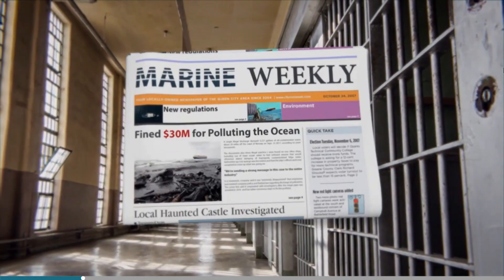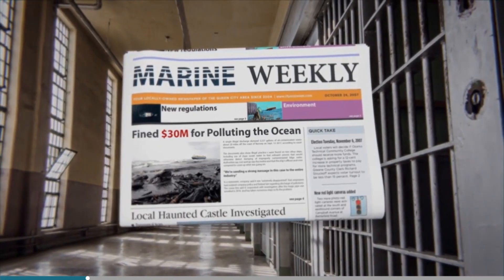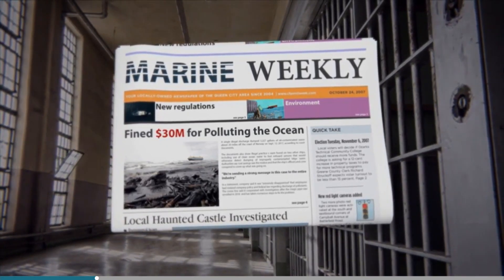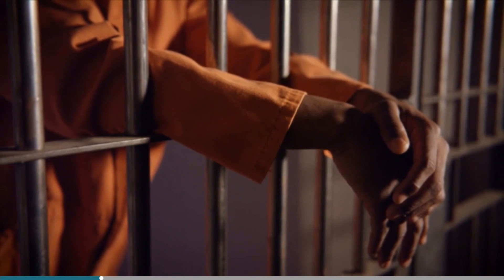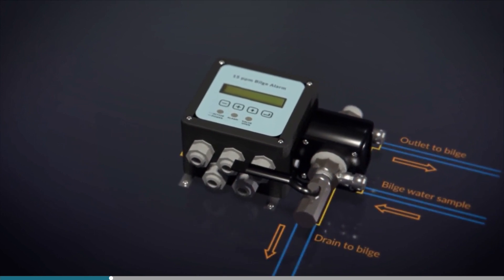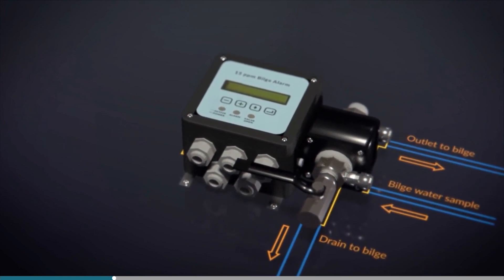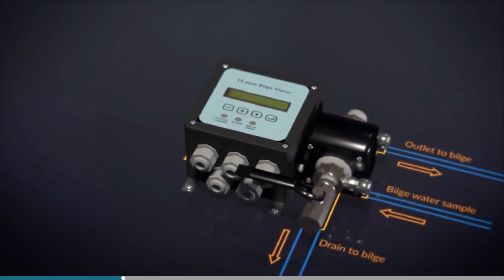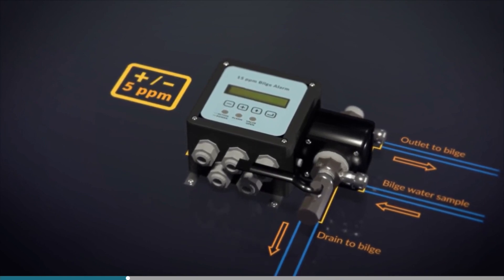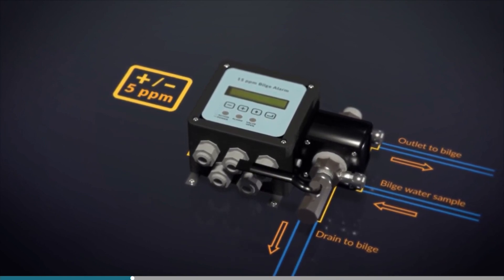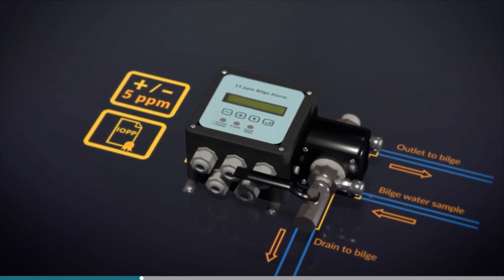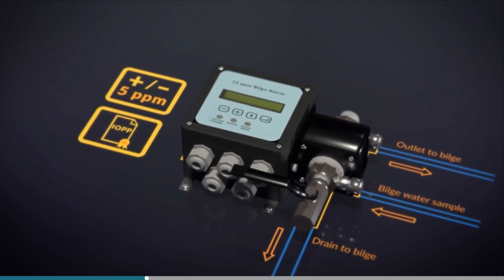Others have deliberately bypassed separating equipment altogether, with arrangements referred to as the 'magic pipe.' Such arrangements are illegal and immoral, and have led to prosecutions, jail sentences and heavy fines. The oil content monitor will have anti-tamper seals to prevent unauthorized alterations. A 15 ppm bilge alarm must be accurate to within plus or minus 5 ppm, and it must keep this accuracy even if there are other contaminants. Accuracy should be checked at IOPP Certificate Renewal surveys in accordance with the manufacturer's instructions.